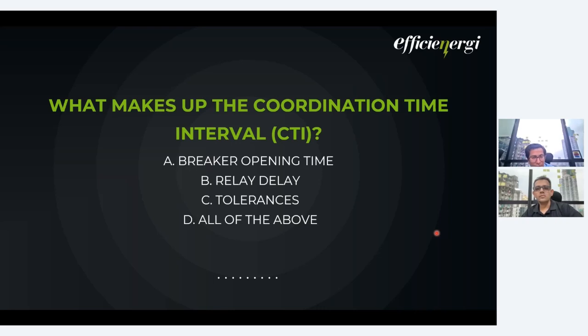Then we don't have knowledge of the transient overreach of each relay. Siemens might have a different transient overreach, and ABB will have a different transient overreach. Then we don't have knowledge of the resetting time, which is also called over travel time, or in standard terms, overshoot time. Those time tolerances we don't have. So normally, as per IEEE 242, the coordination time interval required is in the range of 200 to 250 milliseconds.